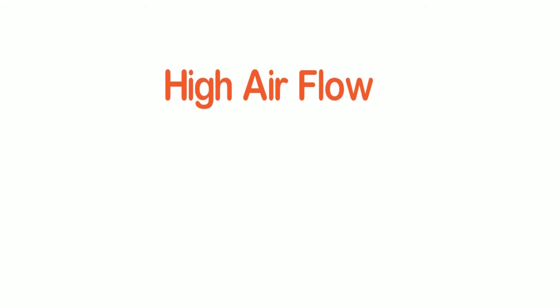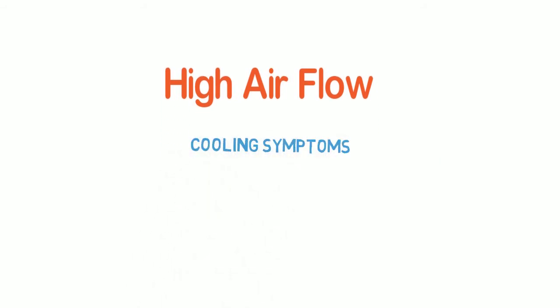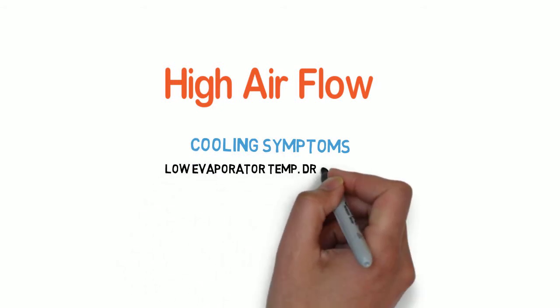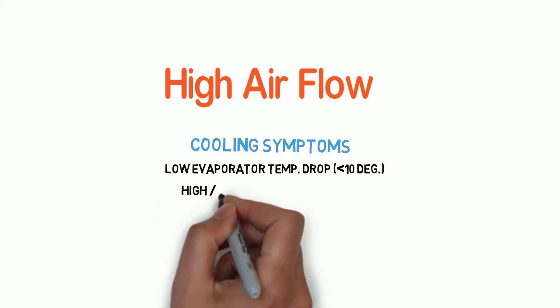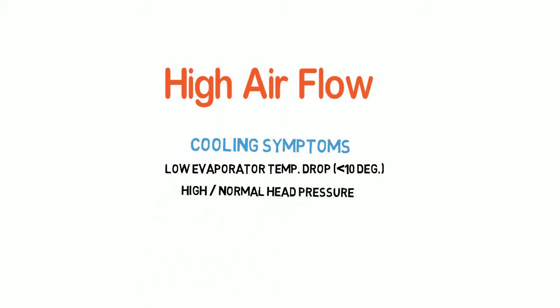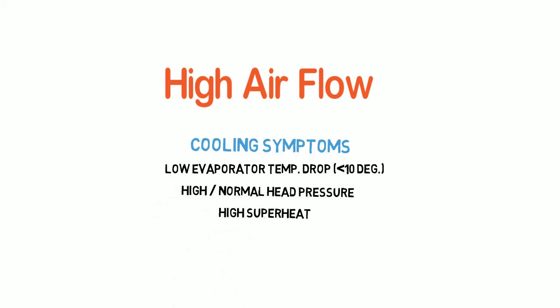Symptoms of high air flow — cooling symptoms: low evaporator temperature drop under 10 degrees, high to normal head pressure, and high superheat.